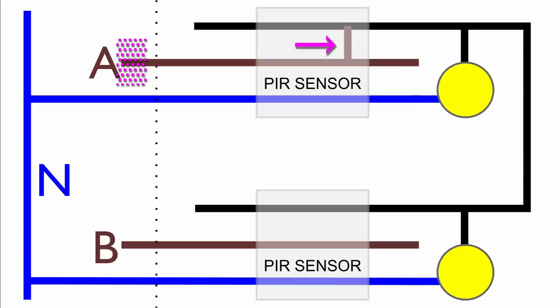Now I don't know what testing was done when this was originally installed about 10 or so years ago, but the problem with this kind of fault and this interconnection here is that if you just tested from the consumer unit on the individual circuits you wouldn't have necessarily found anything wrong. Because those PIR sensors are permanently connected it's fairly likely that somebody just did an insulation resistance test by connecting line and neutral together for each circuit and then testing between that and earth, so that wouldn't have shown any connection between the circuits. The only way in this configuration that this fault would have been detected is if somebody actually tested between the two neutrals for the two separate circuits, or tested between the two lines for the two circuits. Assuming that the lights were actually installed, they would have got some kind of connection via the light fittings and the PIR sensors, but that's not actually a standard test in terms of the testing that's done on a new installation. Generally it's the individual circuits and you don't generally check for connections between the individual circuits, so it's fairly likely that even if testing had been done at the time this fault would not have been detected.